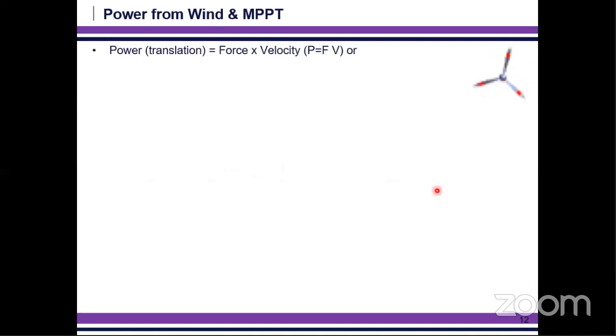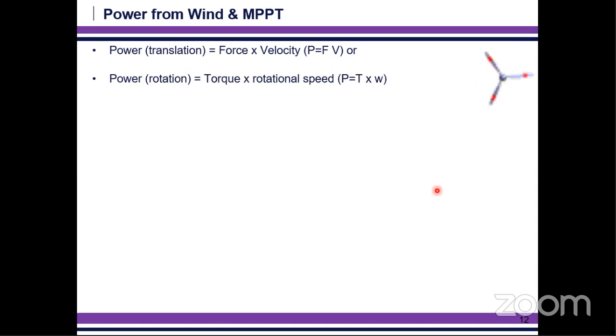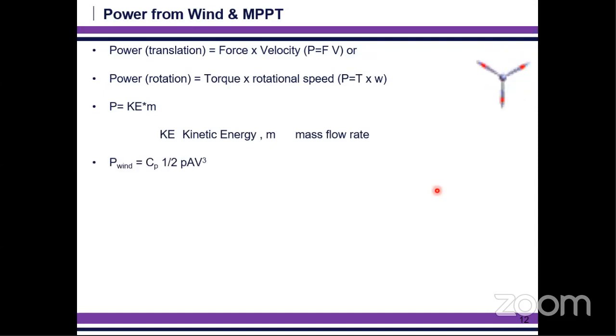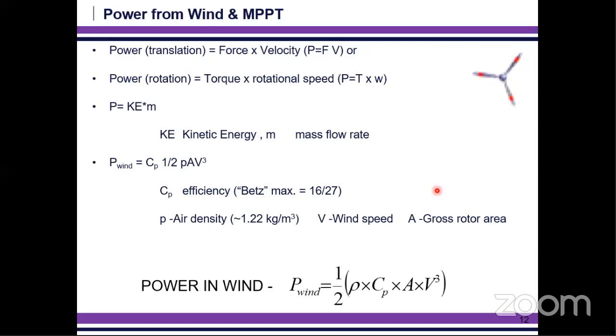Power from the wind is normally the force multiplied by the velocity. If it is rotational power, it is torque, which is nothing but the rotational force. So rotational force multiplied by the rotational speed is your power. If you substitute this, you get the equation: half rho Cp A V cube. So the power is proportional to the air density rho, Cp is the efficiency coefficient, A is the gross rotor area, and V is the wind speed.